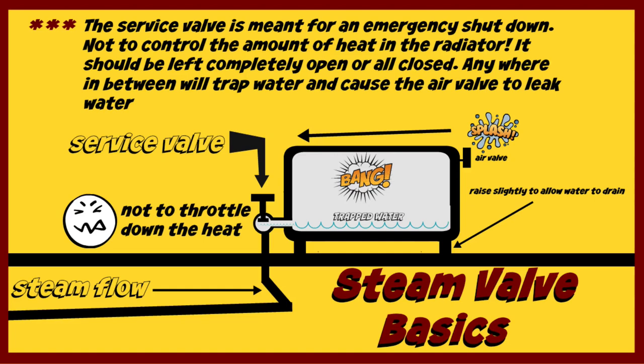This video is specifically about people throttling these valves because they think they can control the amount of heat. To me, these are just plain and simple service valves where you can shut off in an emergency — for example, when the air valves have popped off or someone's attempted to change them and they've broken off. You need to shut the radiator off in a hurry. That's what that service valve is for. You shut it off, tend to the emergency, and turn it back on again. Truth be told, these valves, when installed in most systems, probably 20, 30, 40, 50 years ago, have never been touched. Then all of a sudden people start touching them — they'll start to leak from the stem or from the union connection. When that happens, my policy is to just change the valve.